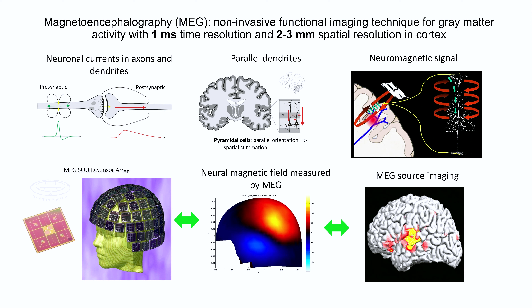When neural currents are firing, they generate a MEG field that can penetrate different head tissue with no distortion. By placing the MEG sensor outside the head, we can perform noninvasive MEG measurements. Each chip has three sensors, totaling 102 chips and 306 sensors. At a specific time — in this case, auditory response — we can measure the field topography with MEG sensors. By solving the MEG forward inverse problem, we generate source imaging, the hotspot, which can be superimposed on the anatomy we get from MRI.